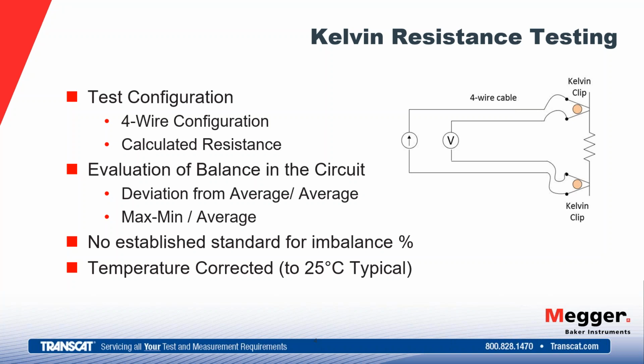is performed in the field. And basically what we're looking at is an imbalance value that we're going to compare to a threshold. So for deviation from average, generally we're at 2.5 to 3%. Max minus min over average, around 5%. And anything over that threshold, we're going to consider as being imbalanced and something that we need to investigate in order to correct that issue.